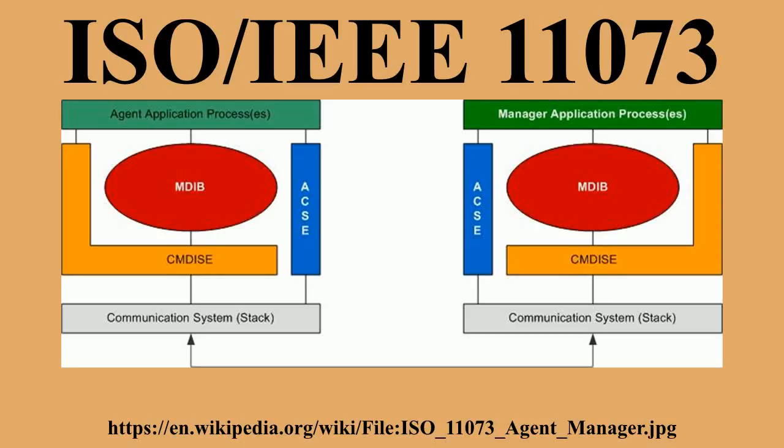They comprise a family of standards that can be layered together to provide connectivity optimized for the specific devices being interfaced. There are four main partitions to the standards: device data, including a nomenclature or terminology, optimized for vital signs information representation based on an object-oriented data model, and device specializations; general application services; internetworking and gateway standards; and transports.